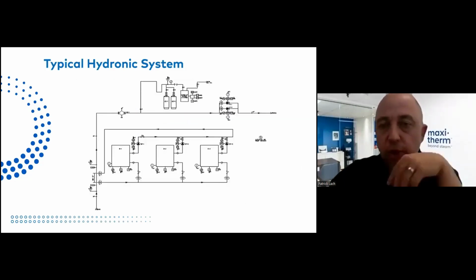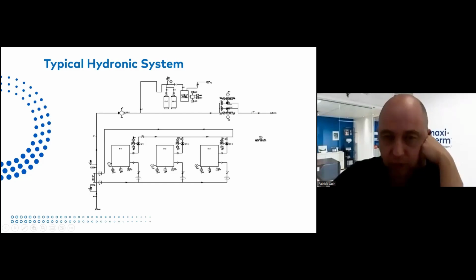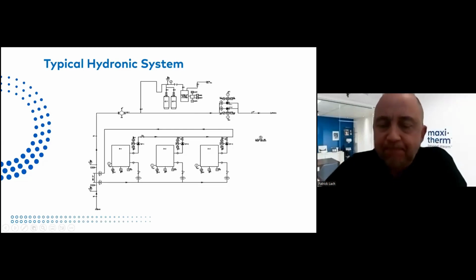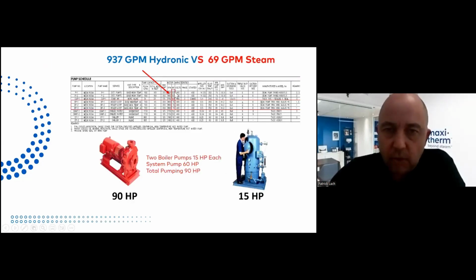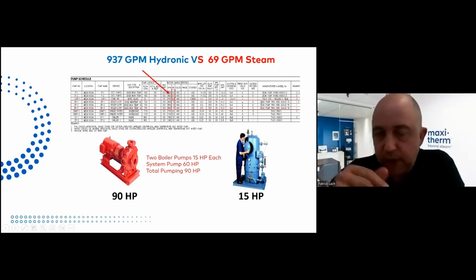Okay, so for the hot water design, they had an N+1 boiler room here, 3 boilers, 1 is a backup. Each boiler needs a pump to get in the loop, and you need big pumps to feed the building, right? So this specified a 60 horsepower main pump for the main loop, and each boiler needs a 15 horsepower pump, right? So for a total of 90 horsepower in operation. If you put a feed water tank like this right on the floor, no head pressure, right? It's not like 30 feet high, you will need a 15 horsepower pump. Kind of an easier fix, in my opinion.